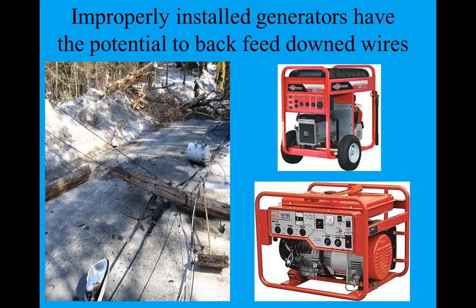And unfortunately, what we're finding more and more during storms is people drag this generator out. They don't read the safety manual. They don't have a code-approved switch, and they're plugging that 240 plug into the dryer outlet, and they're backfeeding their entire house. They think they can just go down and open the main breaker, which disconnects the two hot lines from the street, but there's no interconnect on that. Or they even forget to open the main. And they can backfeed through their secondary to that transformer that's on the ground, and maybe the power's been out for a week. And somebody just got home with a generator, first generator they ever owned, plugged that in, didn't read the book, didn't do it properly.